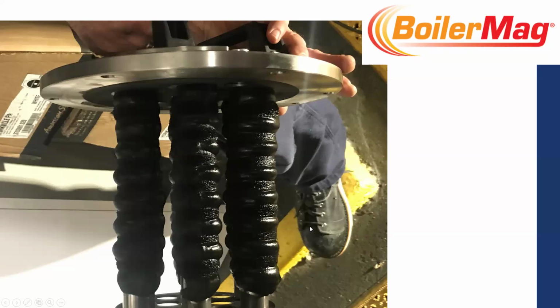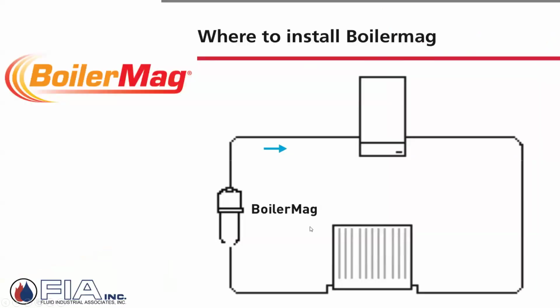And if you didn't have this filter, it would show up at the pump. Because on the back side of that impeller, that's the wet part, is this magnet. And all of a sudden the pumps go to turn on and they've got all this iron filings that start to build up around the impeller. So it's just become common practice as this new technology is not that new anymore, but it's out in the field. You might be also specifying some type of magnetic filtration to pick up any of the sediments that are out in that system. It's very good practice, design practice.